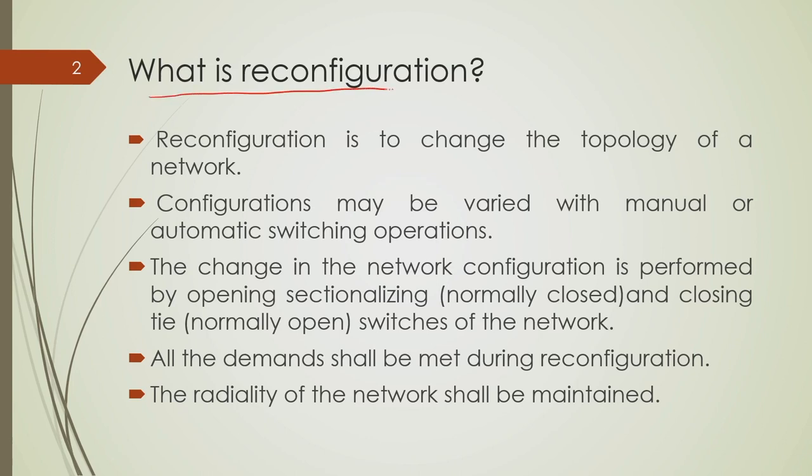Now, first question is, what is reconfiguration? What do you mean by reconfiguration? Reconfiguration is basically a change of network topology or structure. And this reconfiguration may be done with manual or automatic switching operations. So, basically in one word, the reconfiguration of distribution network is to change the network structure or topology by changing the status of sectionalizers and tie switches.